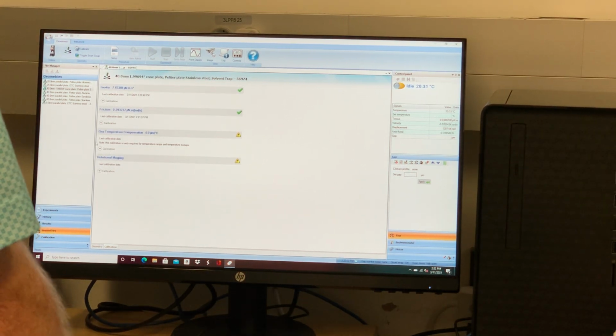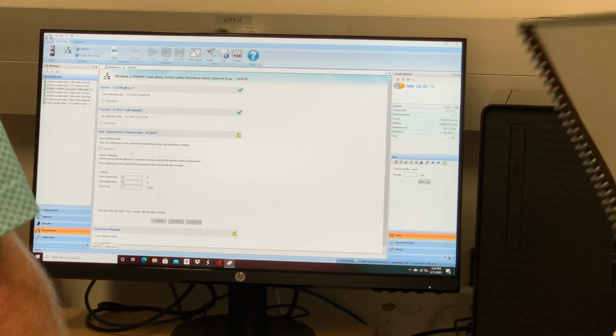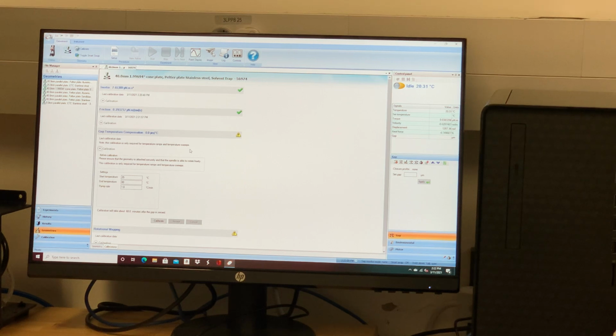The next calibration here is the gap temperature compensation calibration. I do not run this calibration, because it can take a long time, and if I did it for every geometry, I might be here all week. So you guys can run it. Basically, what this calibration does is compensate for heat expansion. When you're heating this up and this up, they're going to expand, and when they expand, your gap changes. Your gap is one of the variables for rheology. It's a very important variable, and this calibration will correct for that.